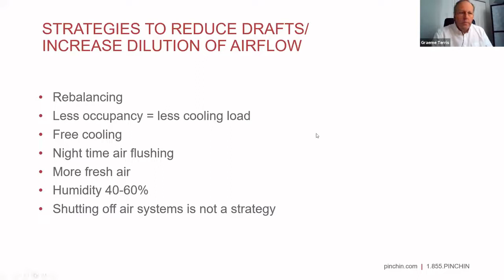Washrooms are an issue, as Jeff mentioned. What a lot of people have done is they've closed off one in every two cubicles just to keep the social distancing. When you flush a toilet, there is aerosol pushed into the air. Generally, toilets work on a decent air change rate, and their extract grills are over the toilet areas, so your drafts aren't quite so much of a problem. But what you really need to do is make sure you operate that system 24/7. If it operates with a light switch, try and recalibrate it so it operates full time rather than on the light switch or on personnel detection or anything like that.